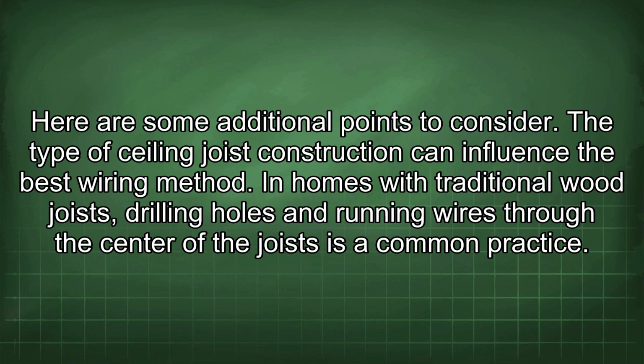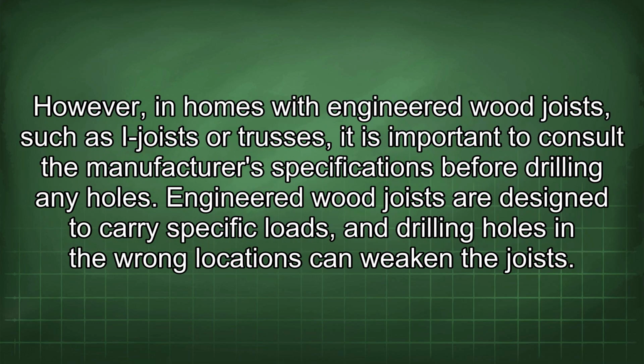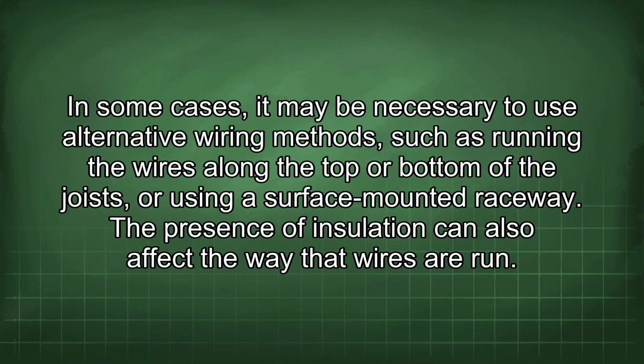Here are some additional points to consider. The type of ceiling joist construction can influence the best wiring method. In homes with traditional wood joists, drilling holes and running wires through the center of the joists is a common practice. However, in homes with engineered wood joists such as I-joists or trusses, it is important to consult the manufacturer's specifications before drilling any holes. Engineered wood joists are designed to carry specific loads, and drilling holes in the wrong locations can weaken the joists.